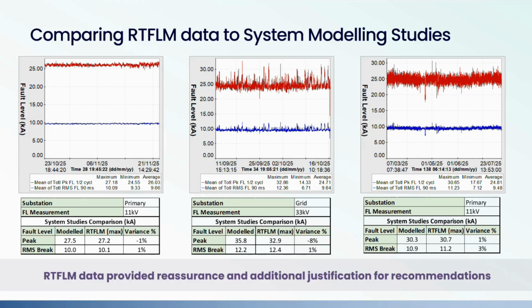And similarly with the middle one, which is a grid substation site where we're measuring 33 kV fault level, in this case the peak fault level from the models is actually 8% higher than what the fault level monitor saw during that time, and the RMS break is within about 1% there. But again, from the trace we can see that there are quite infrequent peaks of fault level, and the majority of the time the fault level is actually lower.